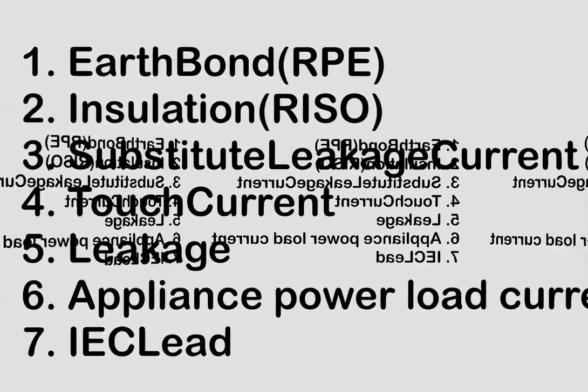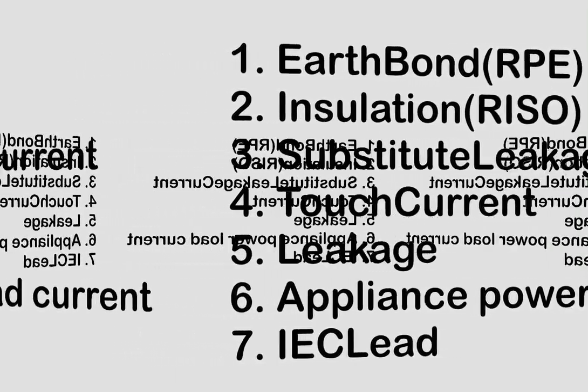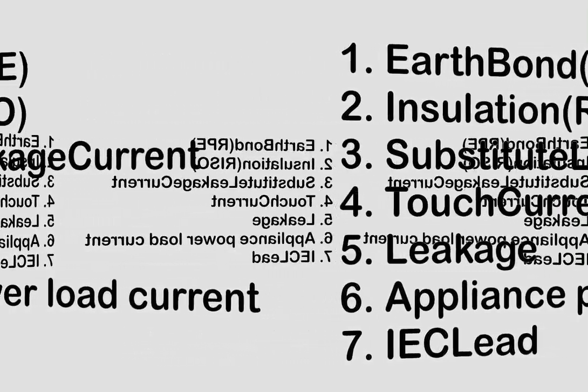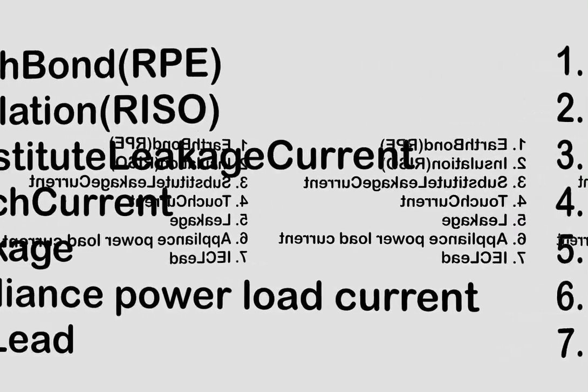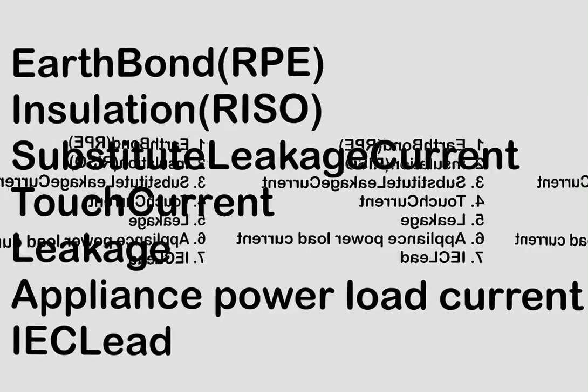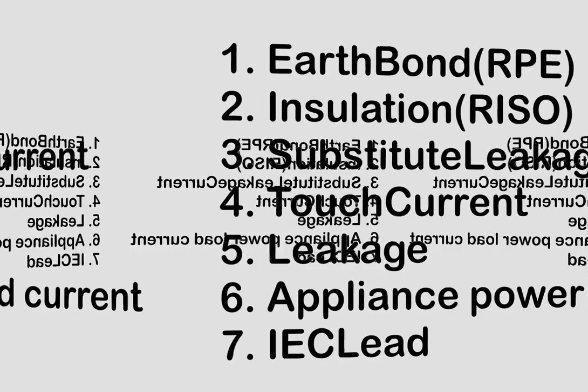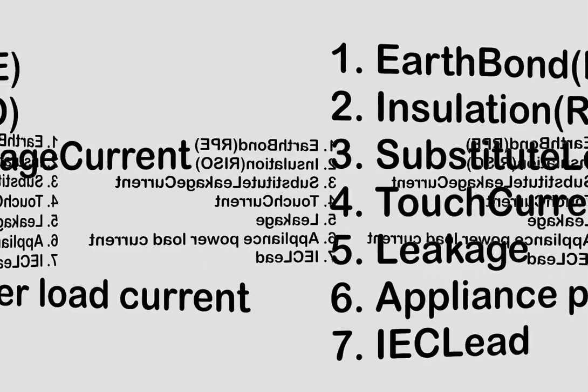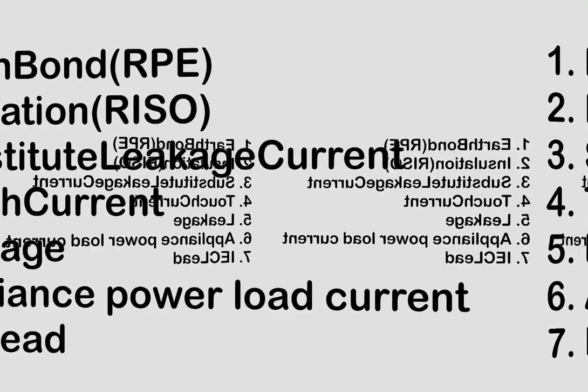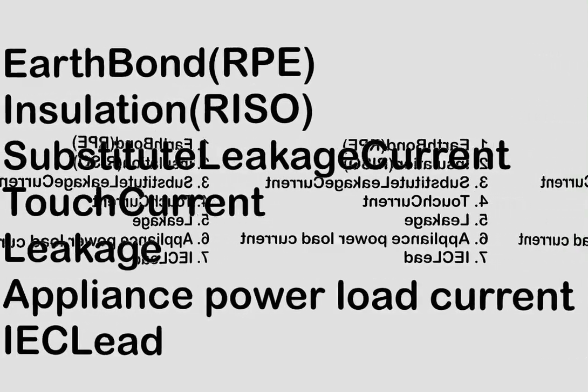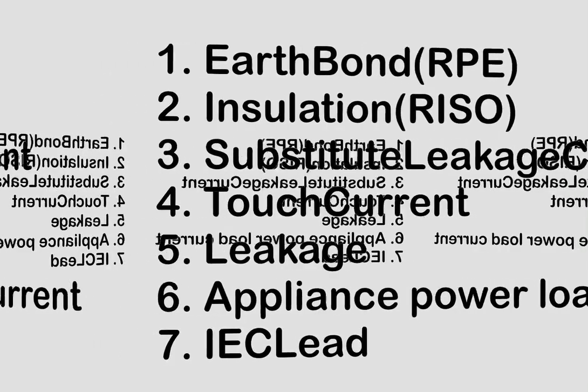Fourth, we need to carry out the touch current test. For Class 2 equipment, there is no earth, so the test lead is connected to an exposed metal part of the body to do the test. Fifth is the IEC lead test. If you have an IEC lead, it should be tested as an individual appliance and recorded and labeled accordingly. Most IEC leads are Class 1 and must have a visual inspection, earth continuity test, and insulation resistance test.